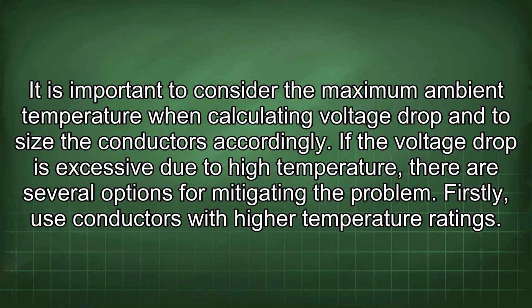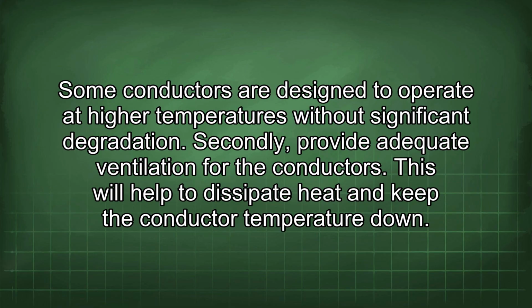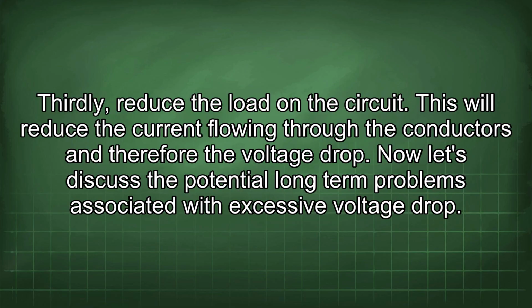Firstly, use conductors with higher temperature ratings. Some conductors are designed to operate at higher temperatures without significant degradation. Secondly, provide adequate ventilation for the conductors. This will help to dissipate heat and keep the conductor temperature down. Thirdly, reduce the load on the circuit. This will reduce the current flowing through the conductors and therefore the voltage drop.